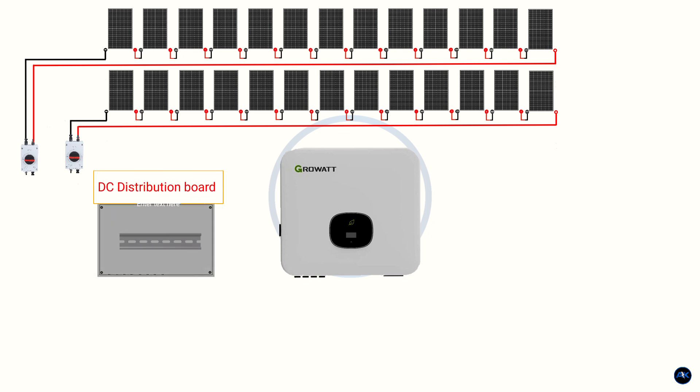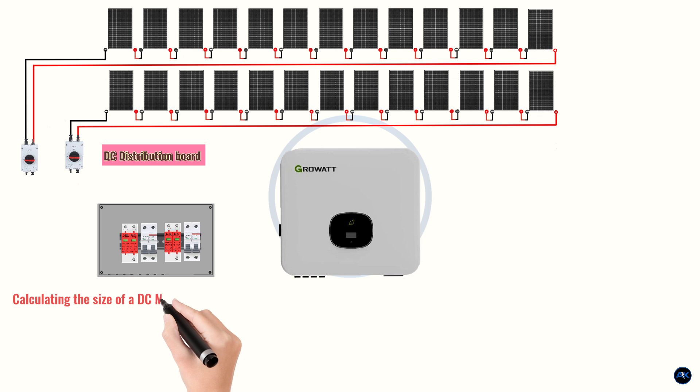DC distribution board or DCDB. A DC distribution board is a panel that houses DC circuit breakers, MCBs, surge protection devices or SPDs, and other components to distribute DC power safely and efficiently. Calculating the size of a DC MCB involves determining the appropriate current rating to protect the circuit from overcurrent and short circuits. Here's a breakdown of the formula and the factors to consider. For a solar string with an I short circuit current of 14 amperes, the recommended DC circuit breaker size would be 25 amperes. Here's the calculation: ISC short circuit current X 1.56 safety factor equals ICB. 14 amperes X 1.56 equals 21.84 amperes. Rounding up to the nearest standard breaker size gives you 25 amperes.